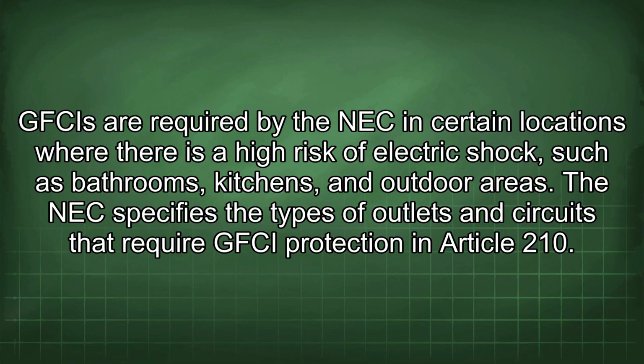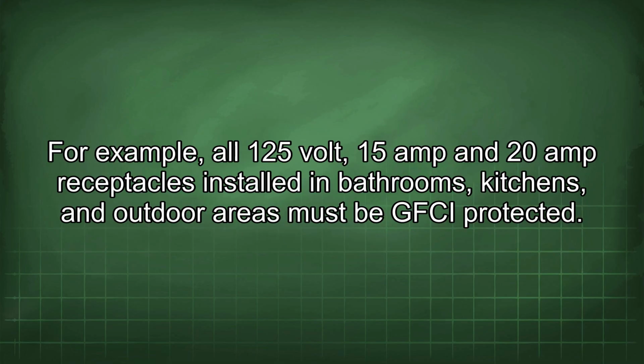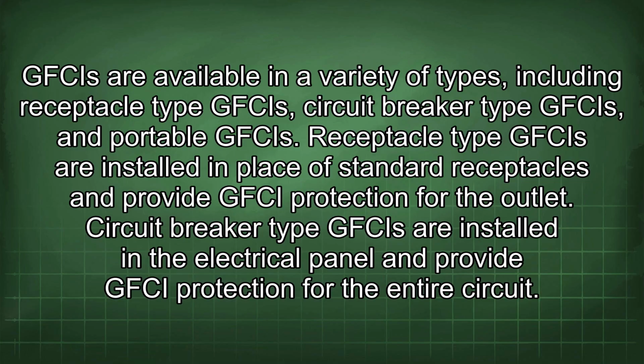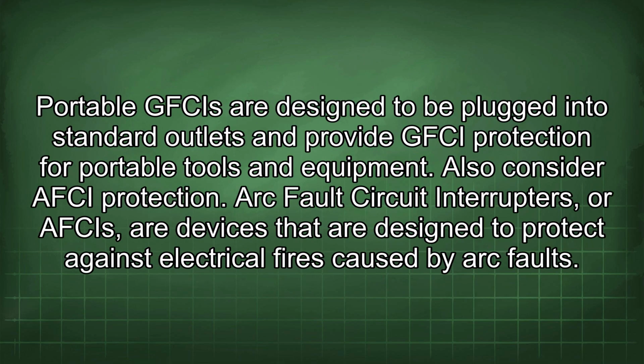The NEC specifies the type of outlets and circuits that require GFCI protection in Article 210. For example, all 125-volt, 15-amp and 20-amp receptacles installed in bathrooms, kitchens, and outdoor areas must be GFCI protected. GFCIs are available in a variety of types, including receptacle-type GFCIs, circuit breaker-type GFCIs, and portable GFCIs. Receptacle-type GFCIs are installed in place of standard receptacles and provide GFCI protection for the outlet. Circuit breaker-type GFCIs are installed in the electrical panel and provide GFCI protection for the entire circuit. Portable GFCIs are designed to be plugged into standard outlets and provide GFCI protection for portable tools and equipment.